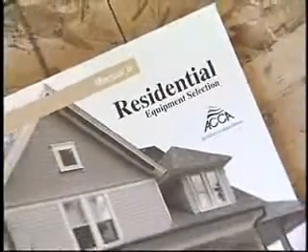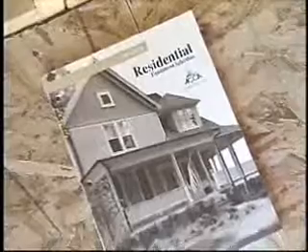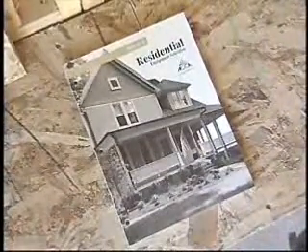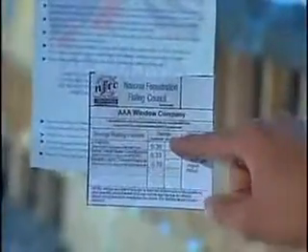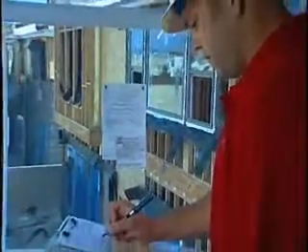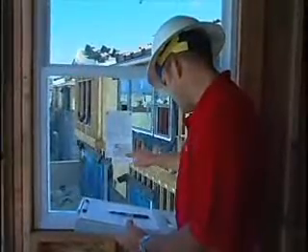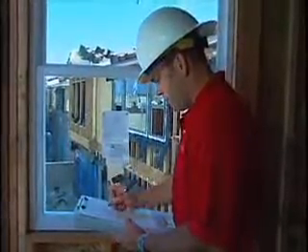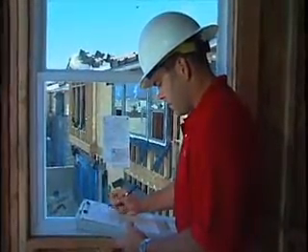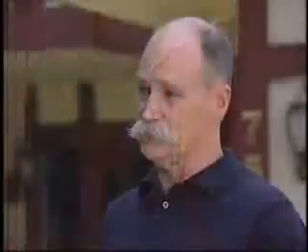And that has to do with the orientation of the structure, the insulation in the walls, basically everything about the thermal envelope that influences the air conditioning load? Sure, and especially the windows. That's a really big thing, when they're not high-tech windows or standard windows. We had one test that was done in Roseville, California, and you had two identical houses, and the only difference between the two was the windows. The one with the really good windows only took a 2.5-ton air conditioner, whereas the one with the standard windows took a 3.5-ton air conditioner to do exactly the same job.